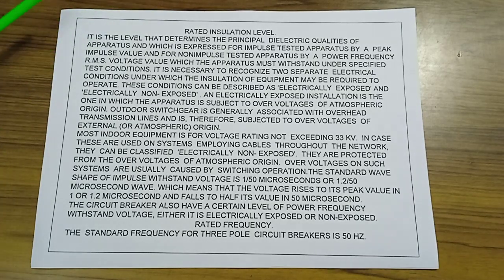Rated insulation level. It is the level that determines the principal dielectric qualities of apparatus, which is expressed for impulse tested apparatus by a peak impulse value and for non-impulse tested apparatus by a power frequency RMS voltage value, which the apparatus must withstand under specified test conditions.